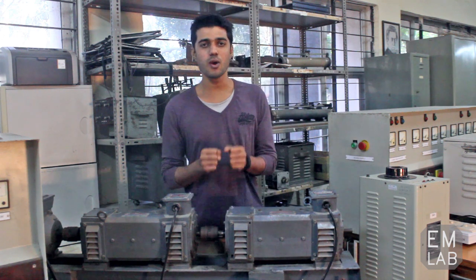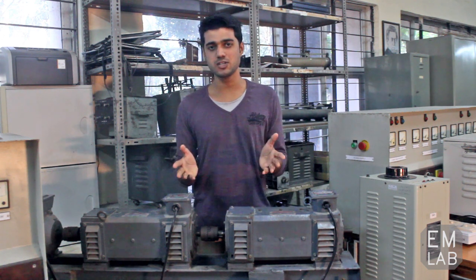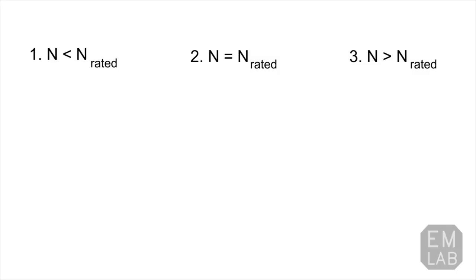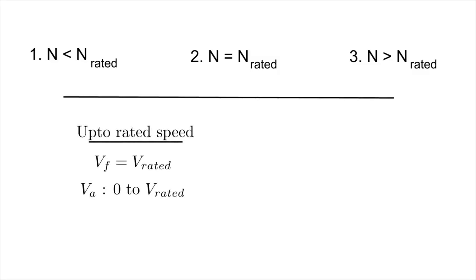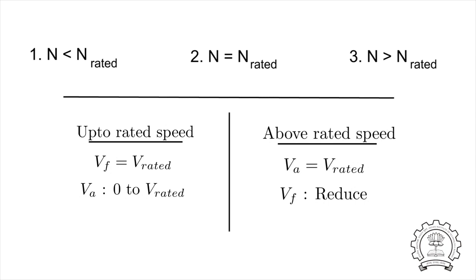In this experiment, we will be operating this DC motor at three different speeds: below rated speed, at rated speed, and above rated speed. Up to the rated speed, we will keep the field voltage constant and we will vary the armature voltage from zero to the rated value. And for above rated operation, we will keep the armature voltage constant and we will reduce the field voltage.